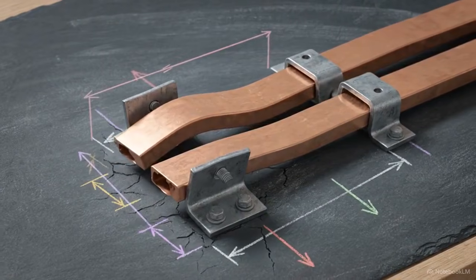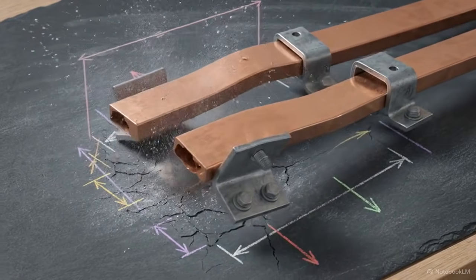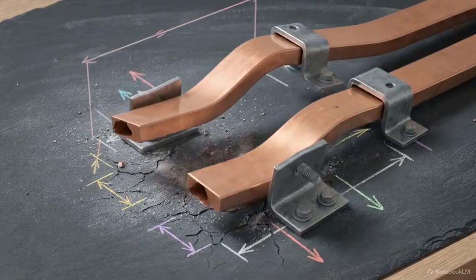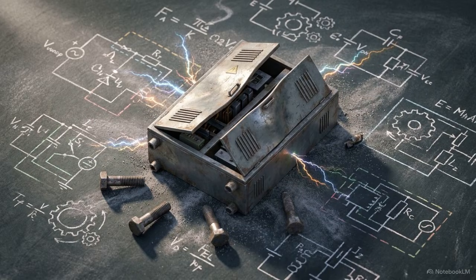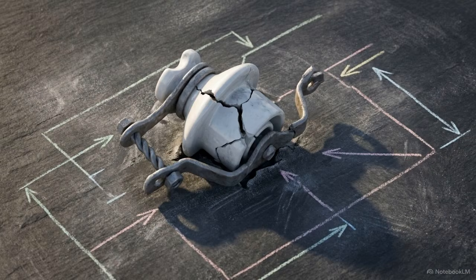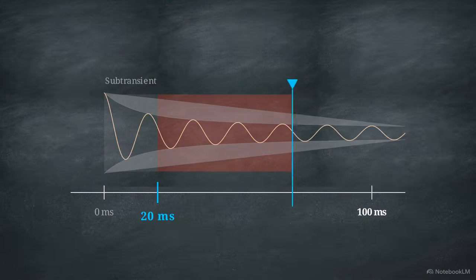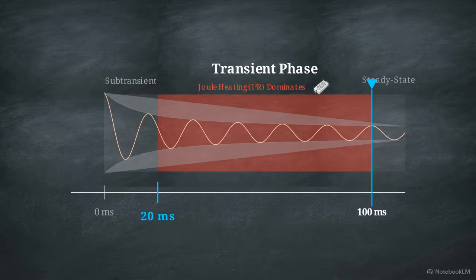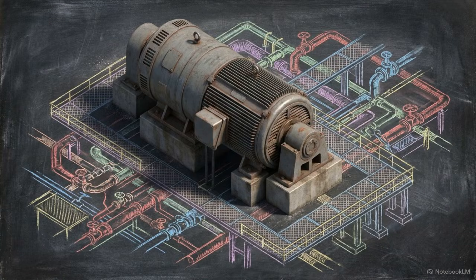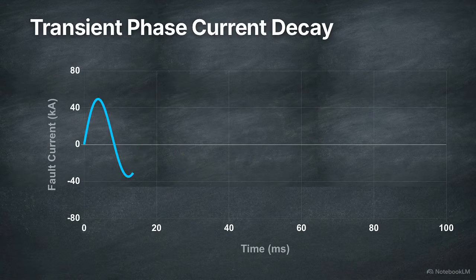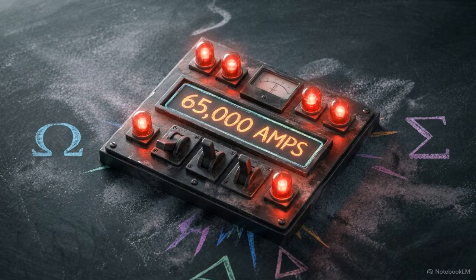Solid copper bus bars violently bow outward, threatening to rip the equipment off its mountings. Before the equipment even has a chance to heat up, the sheer concussive mechanical force of the short circuit begins tearing the system apart. Pushing the timeline forward, we enter the 20 to 100 millisecond window. The massive generators feeding the grid begin to physically react to the sudden lack of resistance, causing the fault current to decay slightly as we enter the transient phase. But that decay is relative.